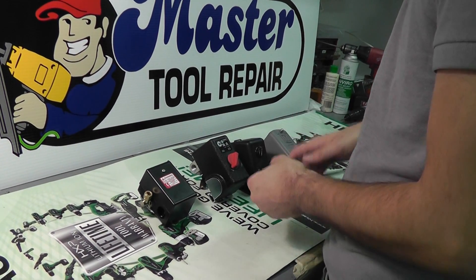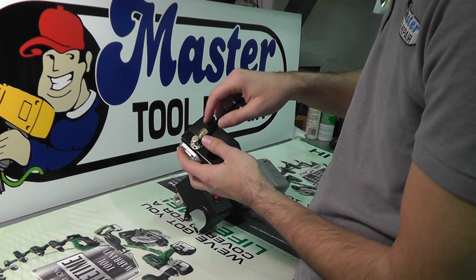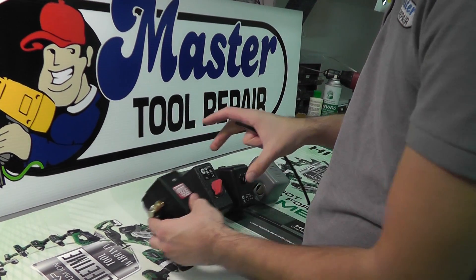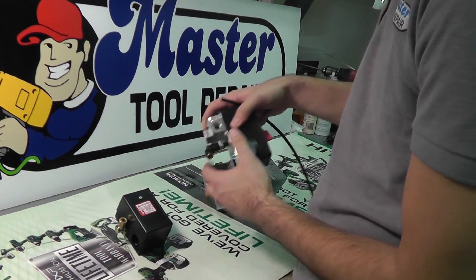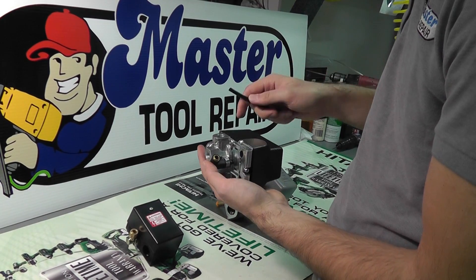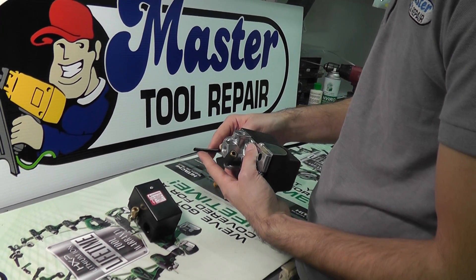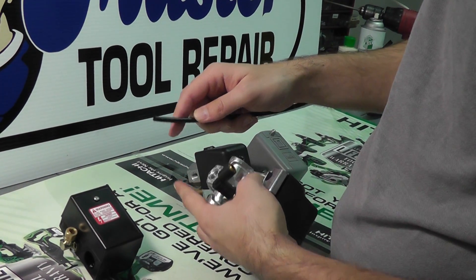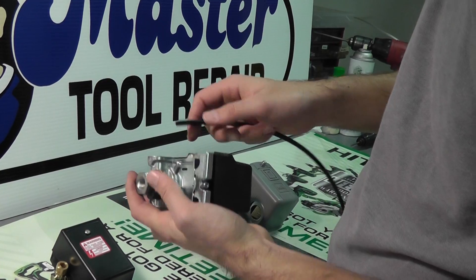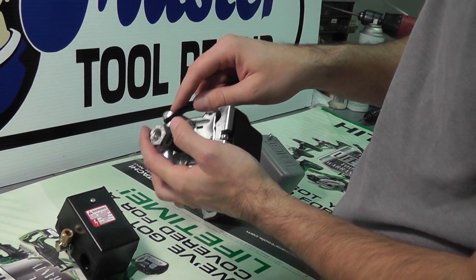Now to attach the unloader tube on your air compressor pressure switch, simply thread it on to the compression thread. Now your replacement might have a different type of unloader valve — a quick connect. If you have a quick connect on your replacement, take your unloader tube, a quarter-inch plastic or nylon line, cut it flush so that there's no angle. Make sure it is flush and clean. You'll simply press it into the quick connect on the unloader valve and the teeth inside will hold it in place.